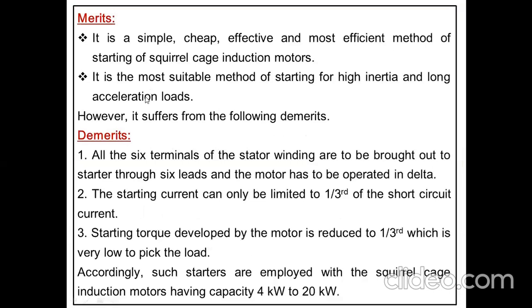Next, let's see the merits and demerits here. It is a simple, cheap, effective and efficient method of starting squirrel cage motors, and it is the most suitable method of starting for high inertia and long acceleration loads. Long acceleration means some types of machines, especially used in industries, have a long period of acceleration, and can withstand the variations there. So in that particular type of machine, we can use this method.